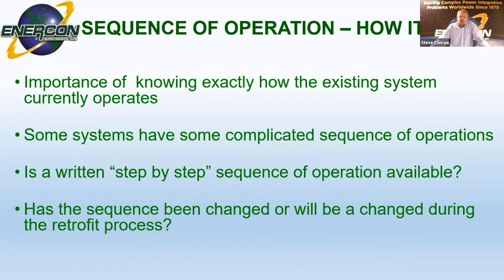We would prefer the customer provide us with an actual step-by-step sequence of operation if it's available. For example, on a retrofit project currently underway in Arizona, the sequence of operation was on placards attached to the front of the gear, and the customer took pictures and sent them to us, which gave us the sequence of operation we needed.